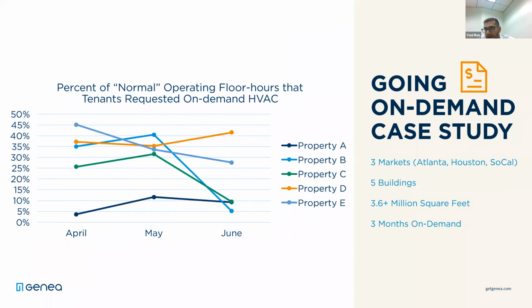As lockdowns began, many of our clients realized that, at least in the short term, they could convert their entire tenant HVAC schedule to an on-demand model and reduce HVAC system operating time and expense. So in Q2 of 2020, we took a sample of 5 client buildings in Genea's portfolio and monitored usage for 3 months. What we found was that tenants requested on-demand HVAC for only 26% of what had been normal operating floor hours.